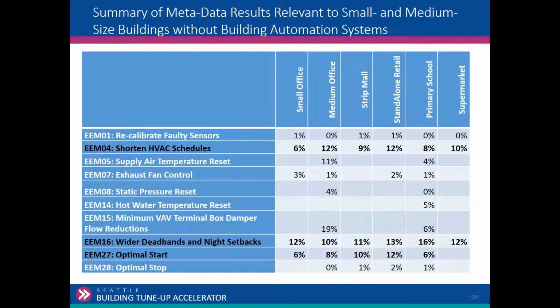So PNNL did a lot of study work on where the opportunities were in these tunings. This was on their small to medium commercial size buildings, by building type. You'll see that calibrating faulty sensors was relatively low, but some of the key opportunities, and this is reiterated in the director's rule, were shortening HVAC schedules. So basically matching schedule to occupancy, or making sure that the optimal start is working and is in place, was a big opportunity across. And these are percentage of savings. These are not additive, but if you just did this point.